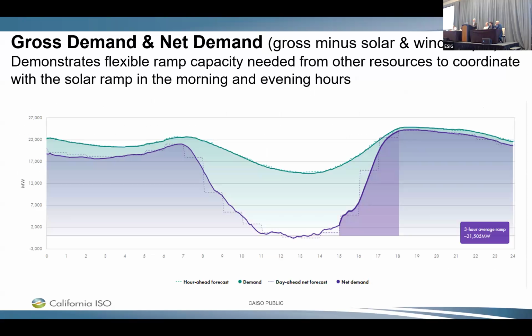There's been some talk about the net demand. This chart here is from the day we had the 21,000 megawatt ramp. You see the gross load at the top, and the net load approached zero that day. We actually did have enough wind, solar, and biogas to serve 100% of our load, but we do have minimum online requirements for a lot of our generation.